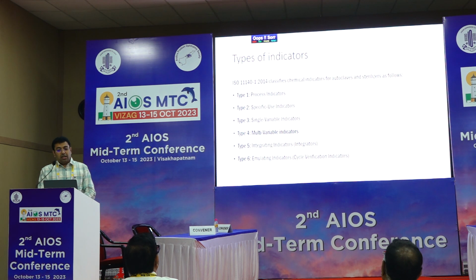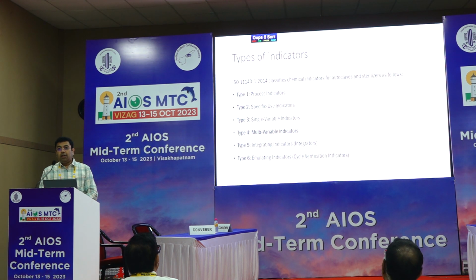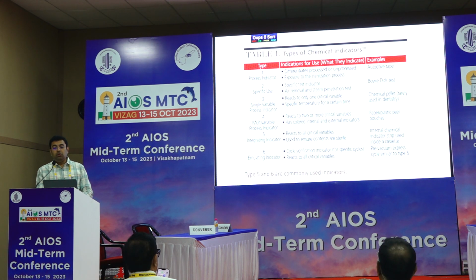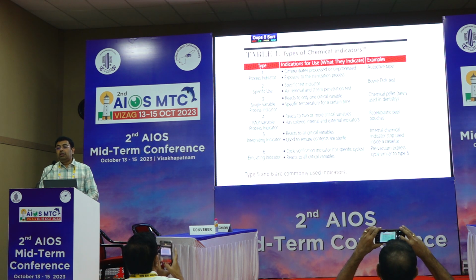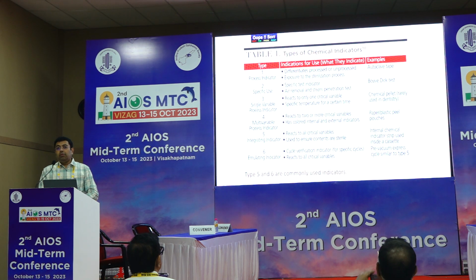So this is the ISO classification of the types of indicators: process, specific use, multivariable, single variable, and all these things. What we normally should be using is type 4 or type 5 indicators, which will test all the components of sterilization like steam, temperature, heat, and all.